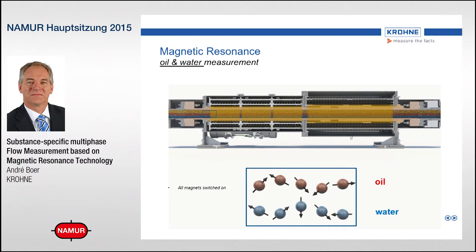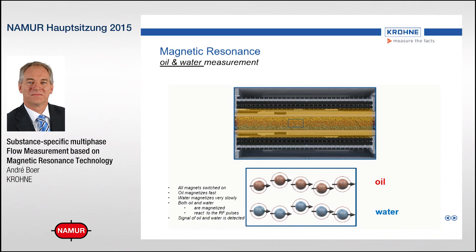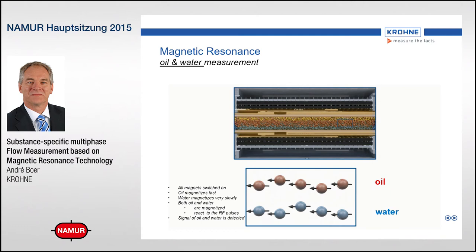In the next measurement phase, we switch on more magnets, so the magnetization time is much longer, giving the water protons the possibility to align as well. Once exposed to high-frequency waves, they also send signals back. So when we do the measurement now, we get signals back from both the oil protons and the water protons — measuring the velocity of both, whereas in the first measurement we were only measuring the velocity of the oil.